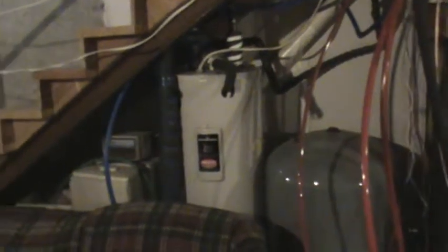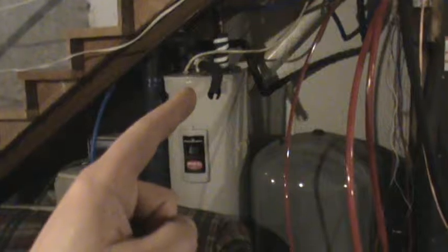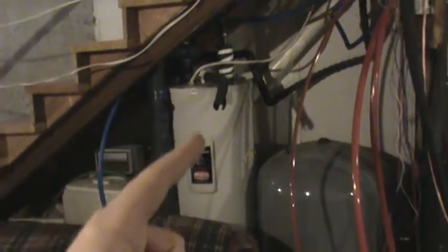What I'm doing to increase the system's efficiency and really monetary efficiency, this is my hot water heater. I'm adding the ability to heat my domestic hot water with the boiler. And so if you look over here, this blue and black thing, that's insulation over what's called a side arm. It's a heat exchanger that I've piped into my system so that eventually I'll have pipes coming out here, and there's one at the bottom you can't see because of my couch. But that's where the hot water from the boiler will flow through the heat exchanger, and then domestic hot water flows through the center of that. They're separated, of course, and can be heated.